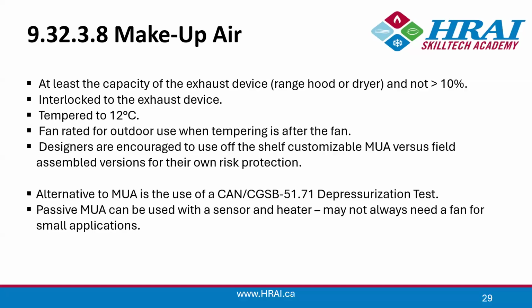An alternative to makeup air is the use of the CAN/CGSB-51.71 depressurization test. HRAI does offer a course that covers that, and you could go ahead with that, but that may or may not just add complexity to the situation. A passive makeup air can also be used with a sensor and a heater. So it may not always need a fan for some small applications. If you do get into those, I'm going to say under 100 CFM, if it's something small like that. I think once you get to about 150, the whole size starts to get a little big.